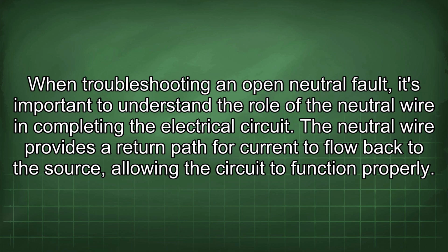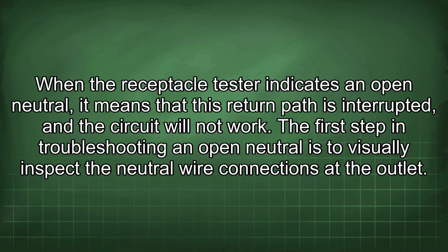When troubleshooting an open neutral fault, it's important to understand the role of the neutral wire in completing the electrical circuit. The neutral wire provides a return path for current to flow back to the source, allowing the circuit to function properly. When the receptacle tester indicates an open neutral, it means that this return path is interrupted and the circuit will not work.